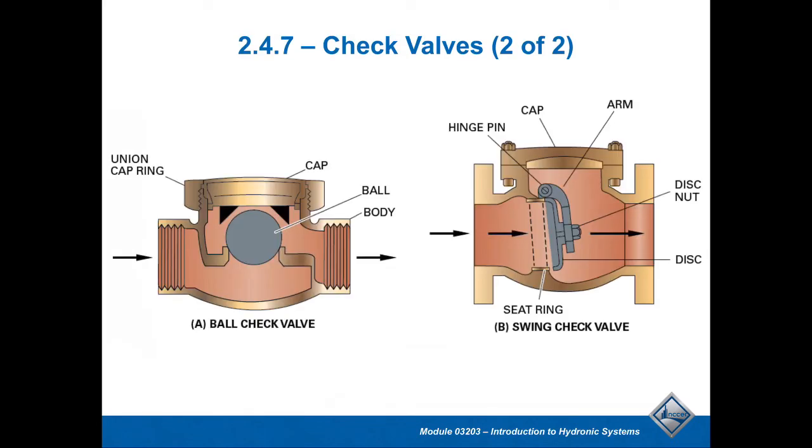All right, so we're going to look at some check valves here next. The first one I want to deal with is a way to prevent flow when we don't want flow to be moving through there. And this type of check valve, what we're going to call a ball type or a swing check valve. One of the differences that you notice usually on some of these types of things is they only allow water flow in one direction. And these generally have very low resistance.